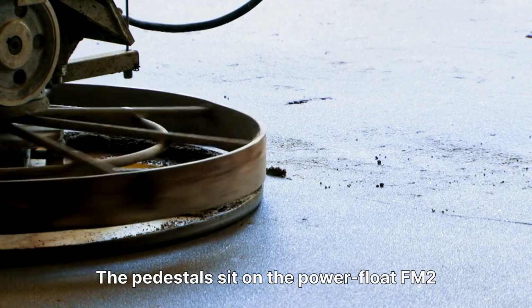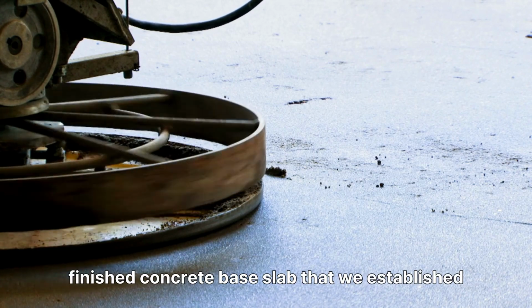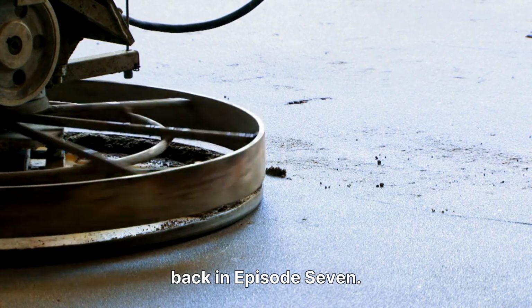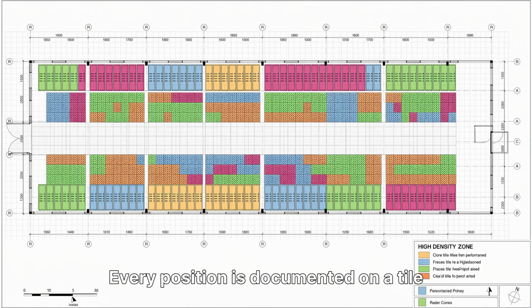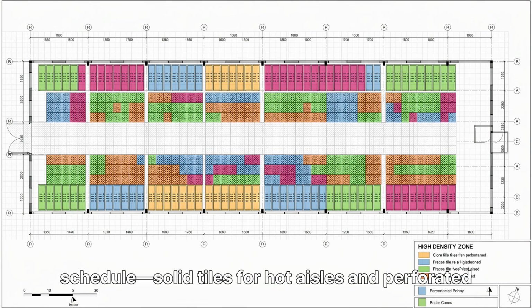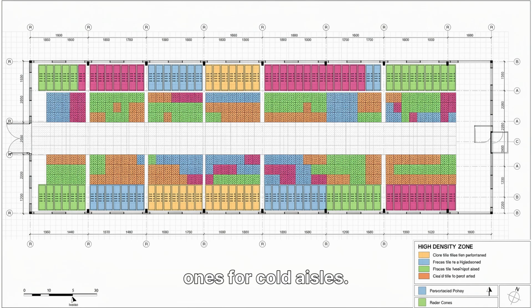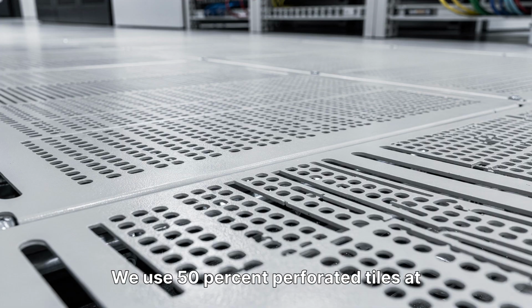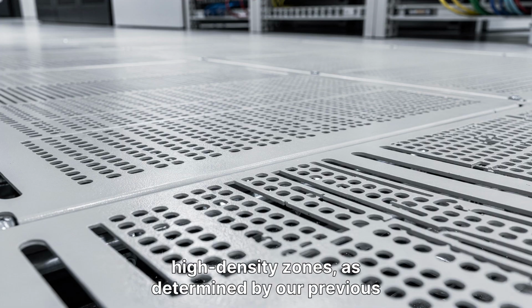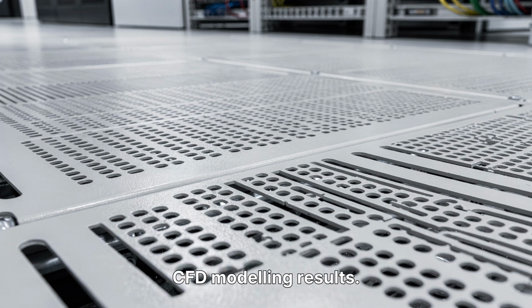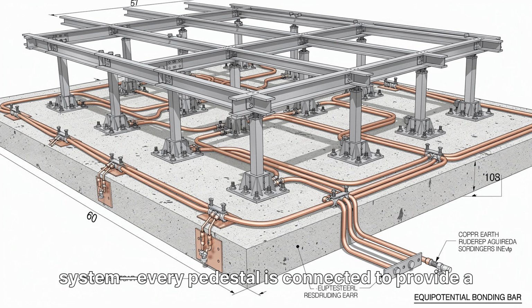The pedestals sit on the PowerFloat FM2 finished concrete base slab that we established back in episode 7. Every position is documented on a tile schedule, solid tiles for hot aisles and perforated ones for cold aisles. We use 50% perforated tiles at high-density zones, as determined by our previous CFD modeling results. The void is bonded to the earth system. Every pedestal is connected to provide a continuous bonding plane.